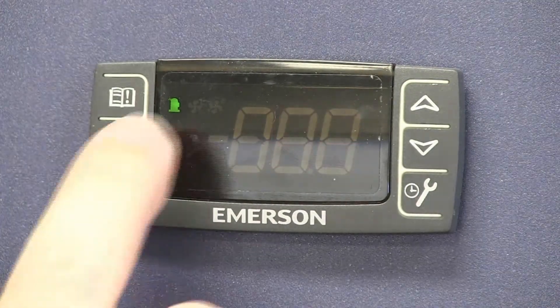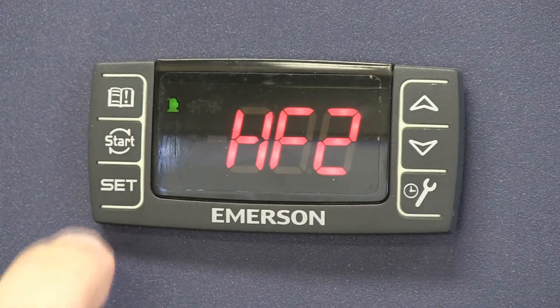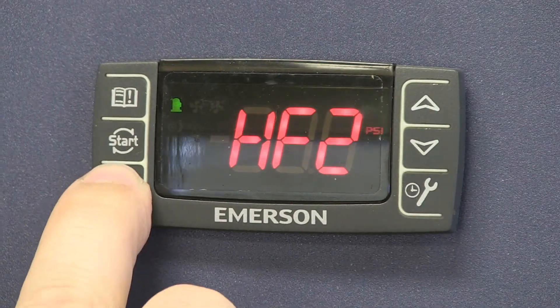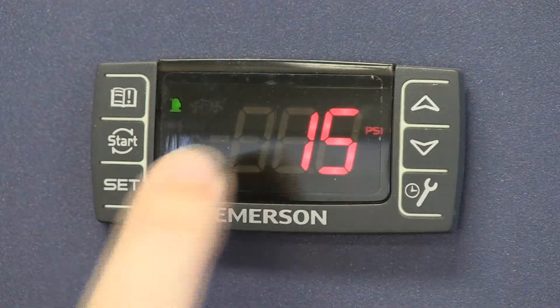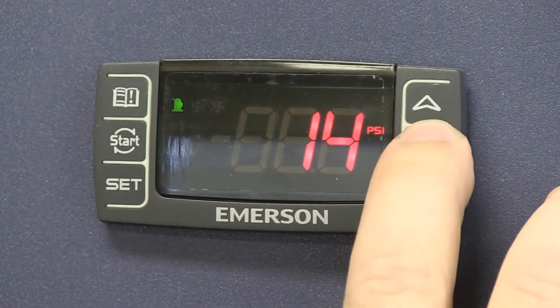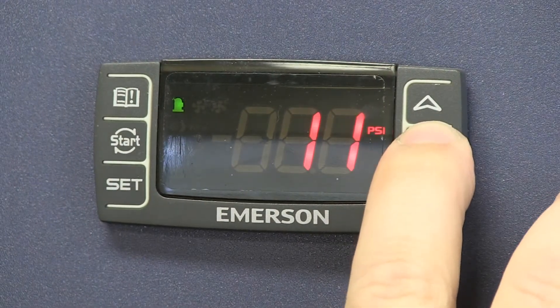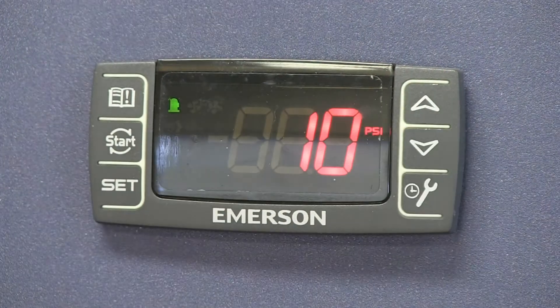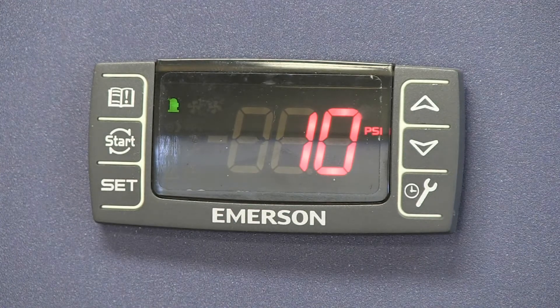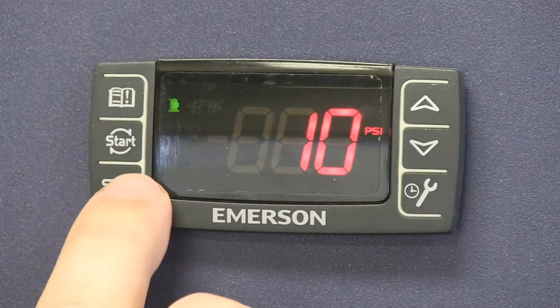And then again, there'll be the differential. HF2 on here is set at 15 PSI. Let's go ahead and lower that down to 10. So that means your cut in for your second fan will be at 105.